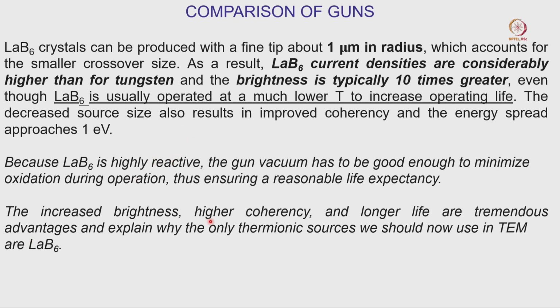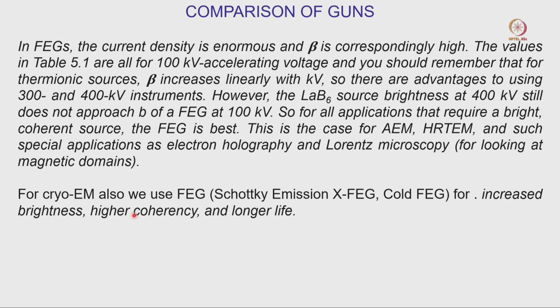So, for a normal thermionic source, nowadays we are always using this LaB6 filament. Now, if you compare to the field emission gun, definitely, as I mentioned, with the field emission gun or Schottky emission gun, the brightness is much higher, it is superior to the other two filaments, and the beam will be much more coherent, and it will help for high resolution TEM as well as cryo-EM.